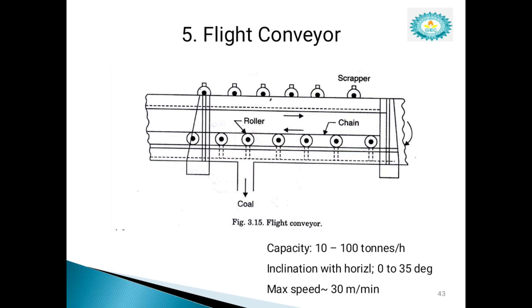And last one is flight conveyor. This conveyor is generally used for transfer of coal when filling of a number of storage bins situated under the conveyor is required. It consists of one or two strands of chains to which steel scrapers are attached. The scraper scrapes the coal through a trough and the coal is discharged at the bottom of the trough as shown in figure. The capacity is 10 to 100 tons per hour and inclination with horizontal angle is 0 to 35 degrees. The maximum speed is 30 meters per minute. These are the equipment used in coal handling process.